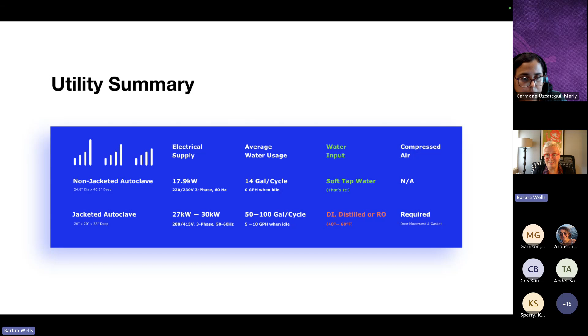The figures shown here are based on the published specs for a 20 by 20 by 38-inch chamber, which is a standard in the autoclave industry, and a comparable 320-liter non-jacketed chamber running a single vacuum cycle. The consumption differences are truly substantial.